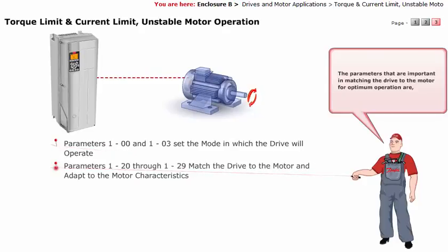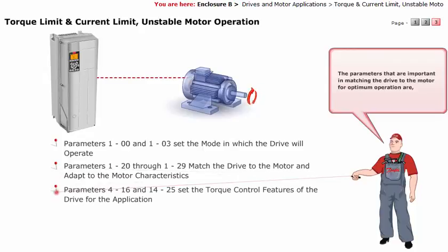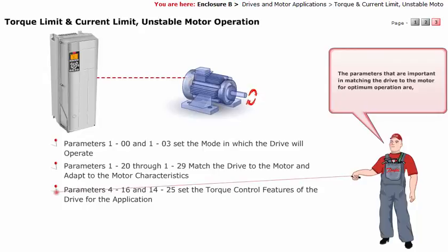Parameters 1-20 through 1-29 match the drive to the motor and adapt to the motor characteristics. Parameters 4-16 and 14-25 set the torque control features of the drive for the application.